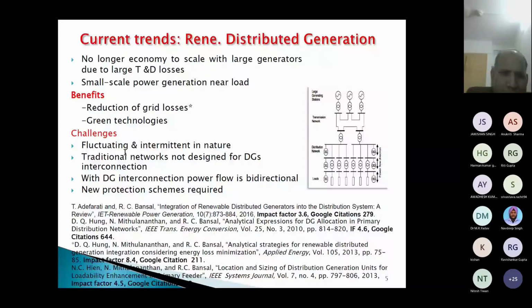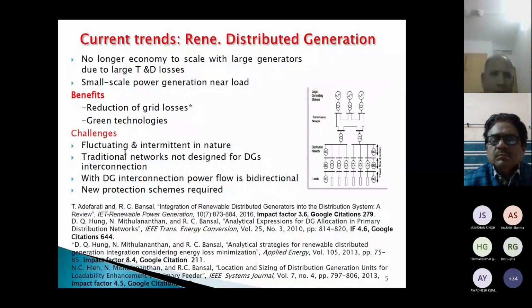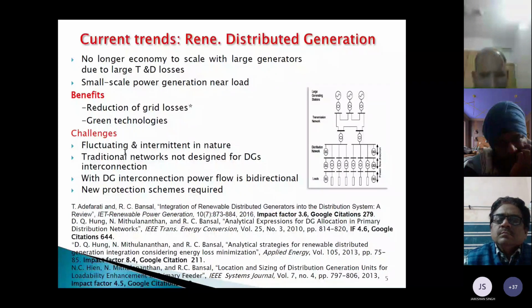Then another major challenge we see is that the power flow became bidirectional. The major issue we face is the protection system. We need significant modification in this protection system. The existing protection system may not work well, because in the traditional power system we use single directional relays, which were less expensive. However, as the power flow becomes bidirectional, single directional relays will not work well. So in that situation, obviously we need to modify the protection scheme to protect our power system.